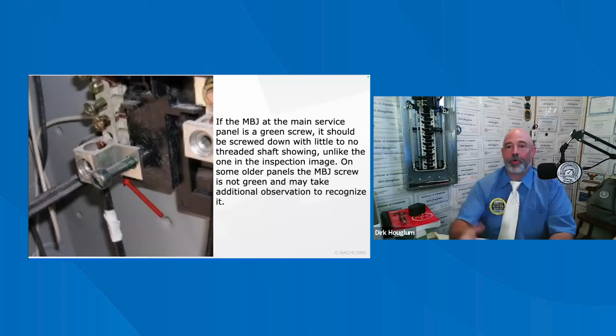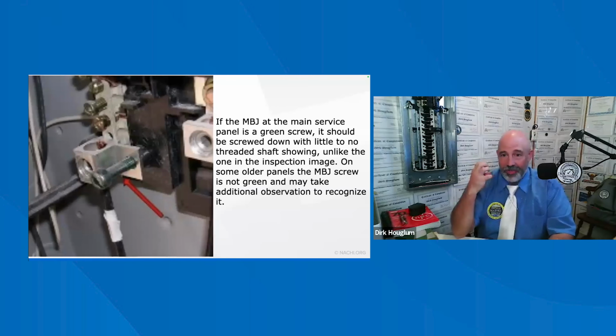I think we keep going over this again because I want to get that in your head. In addition, in distribution panels, the sub-panels, the neutrals and the grounding wires are not combined. And the green screw, if present, should be screwed down. Take a look at this inspection image here. Again, the green screw or MBJ is properly not screwed down at all. This is properly installed because the panel is a sub panel, not a main service panel.